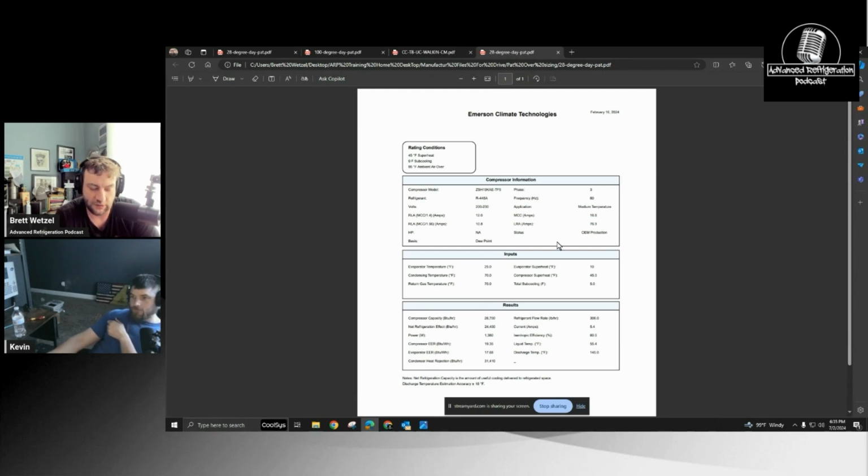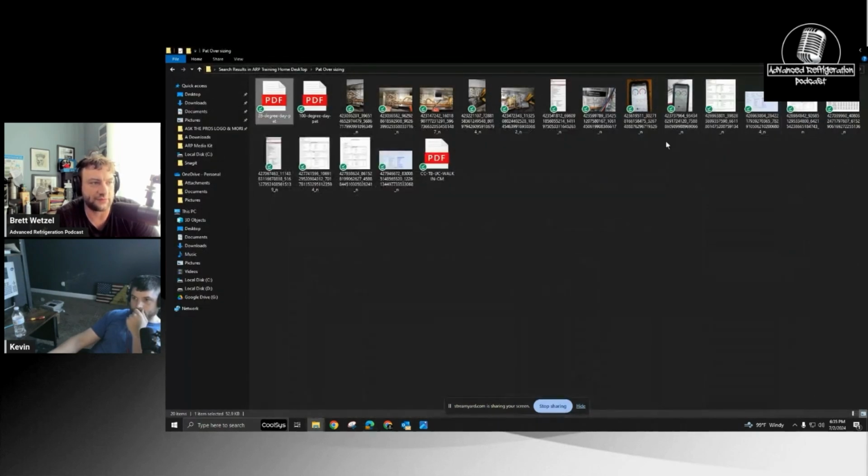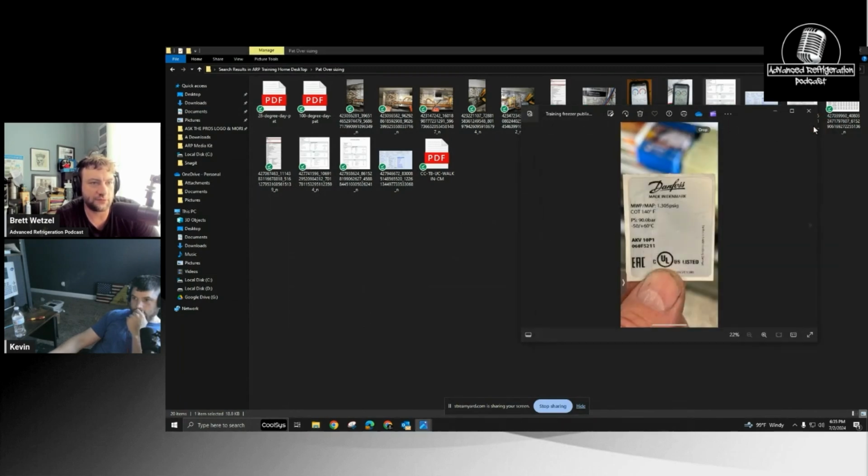So when he pulled one of the condenser fan motor power supplies, the pressure went up, and then the suction pressure came up instantly, and then everything was rocking and rolling. And so he told me the top it ever gets in that area of Indiana, and I don't know where he was at, but he told me it was getting up to top max temperature.